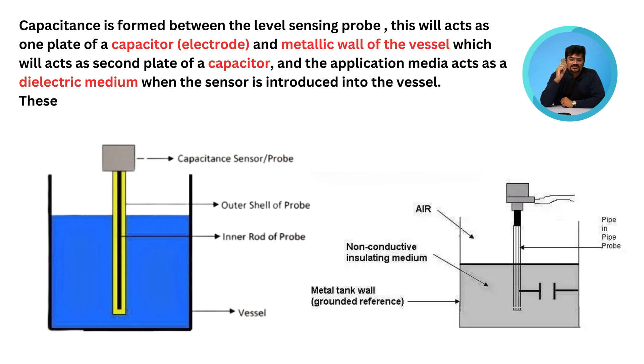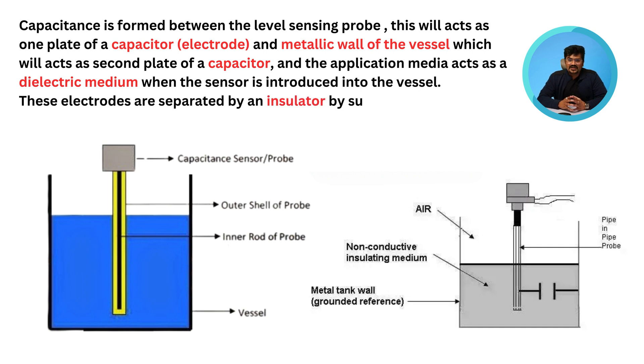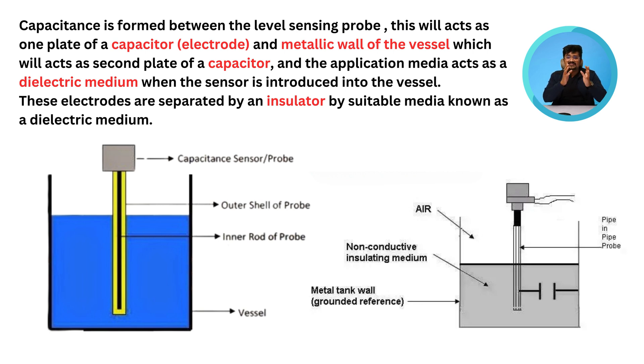The application media acts as a dielectric medium. When the sensor is introduced into the vessel, these electrodes are separated by a suitable media known as a dielectric medium. When the level of the process material rises, the value of the dielectric changes, which results in a change in the value of capacitance between the level sensing probe and the vessel wall. This change can be detected and measured by the capacitance level switch.